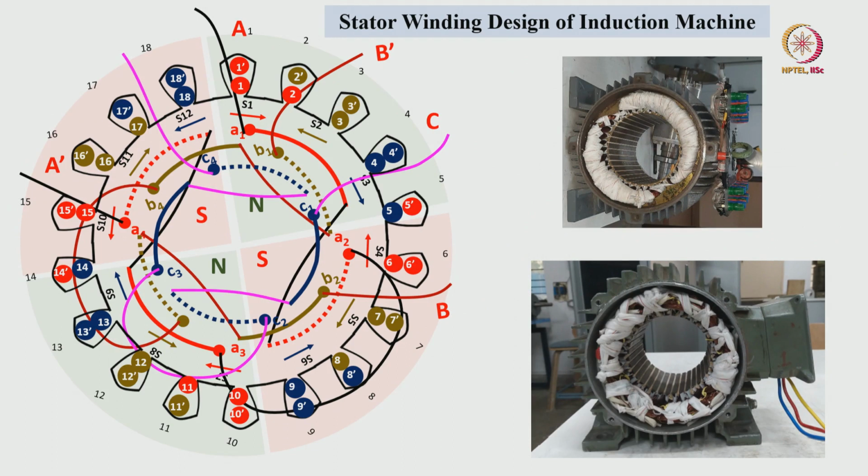So, these are the final connections related to the A phase, B phase and C phase. So, from these 3 terminals we can give the excitations, the other 3 terminals we can make it either star. If it is delta manner, we have to connect all 6 terminals in delta manner and we can excite the machine with 3 phase supply, and end winding threading and varnishing has to be done after making the winding.